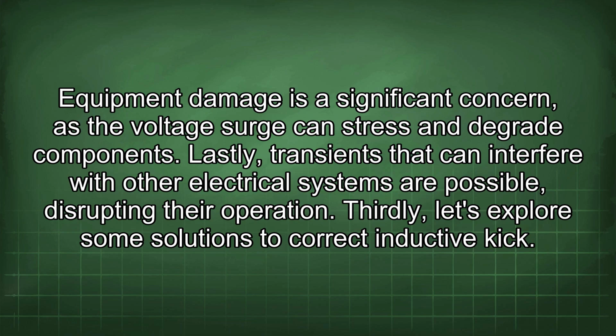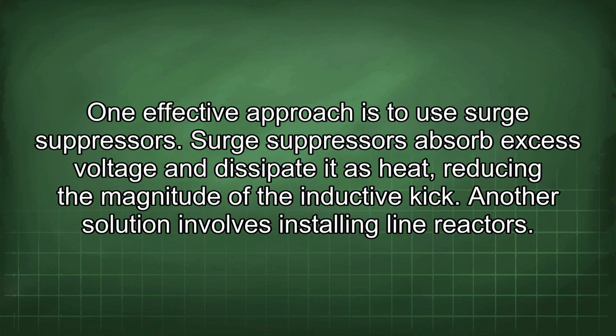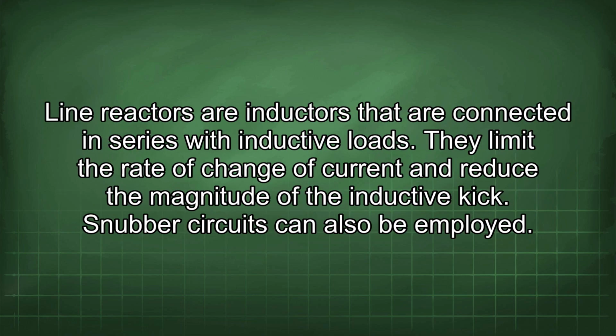Thirdly, let's explore some solutions to correct inductive kick. One effective approach is to use surge suppressors. Surge suppressors absorb excess voltage and dissipate it as heat, reducing the magnitude of the inductive kick. Another solution involves installing line reactors. Line reactors are inductors that are connected in series with inductive loads. They limit the rate of change of current and reduce the magnitude of the inductive kick.